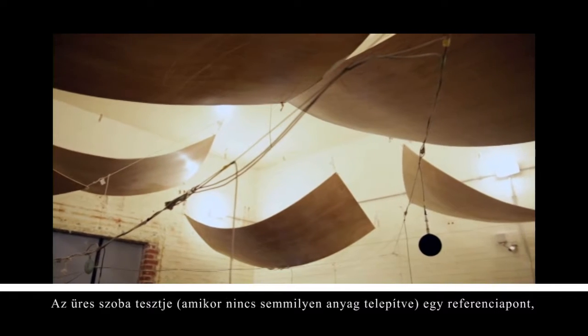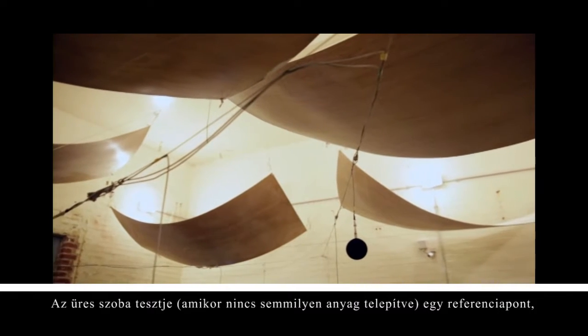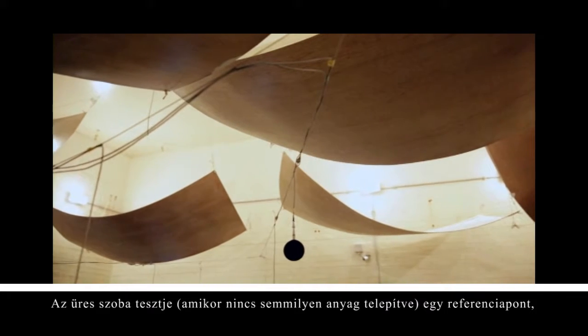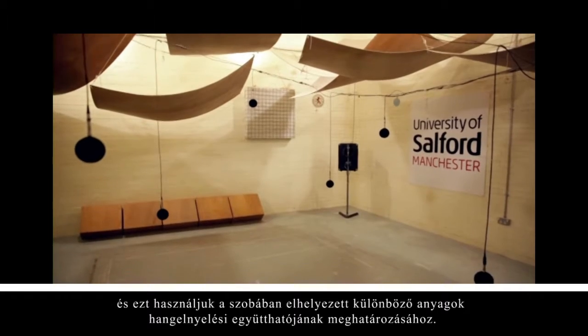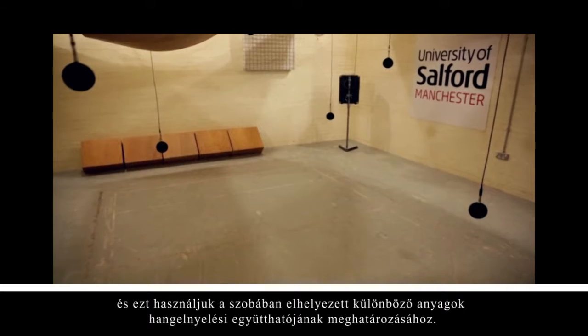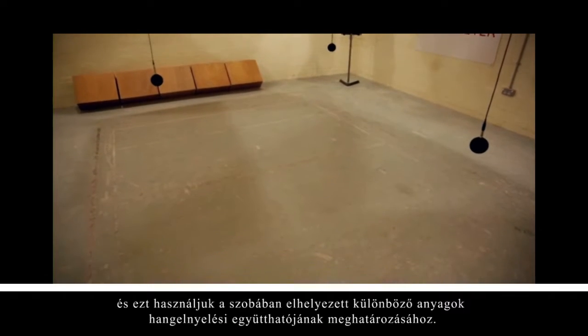The test of the empty room, i.e. no sample being installed, is a reference point, and then we're using that reference to determine the sound absorption coefficient of the sample that's been installed in the room.